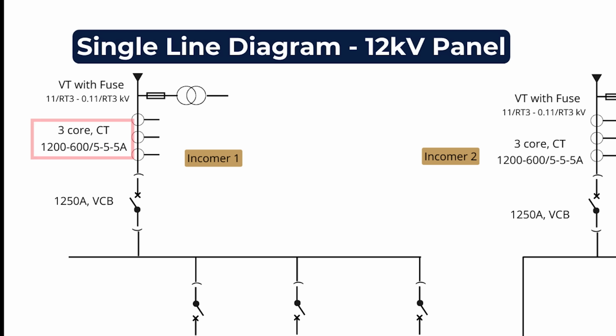Then we have a current transformer. Now the current transformer helps us in measuring the current and also it helps us in giving the inputs to the protection relays that we have. So we are using 3 cores here. So the rating is 1200 by 600 amps. That's the primary current. And on the secondary side, when the current is stepped down, we will have 5 amperes. Okay, it is mentioned 3 times. That indicates we have 3 cores.